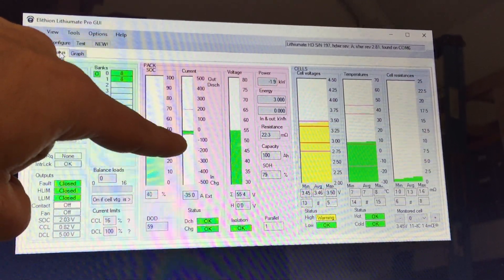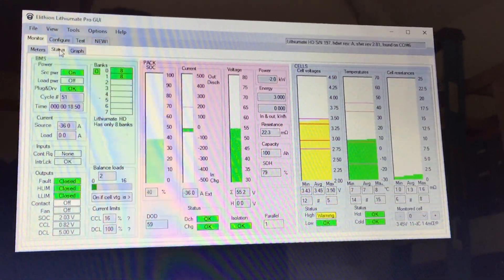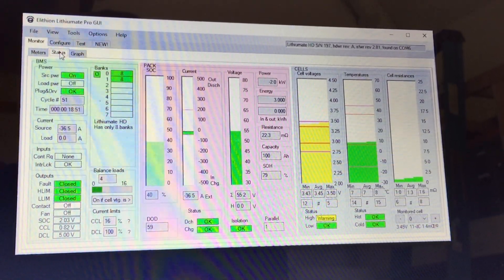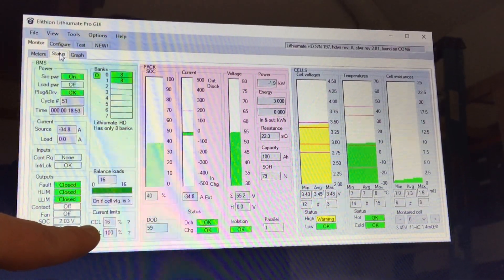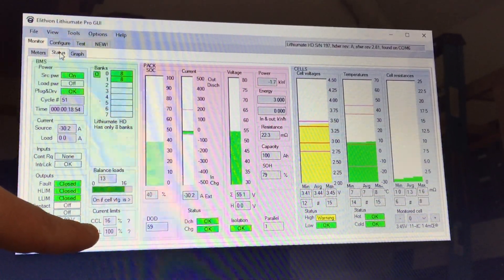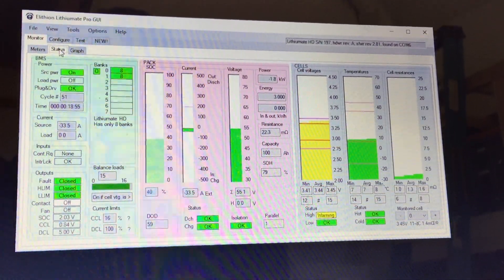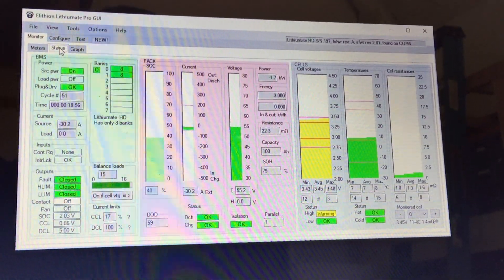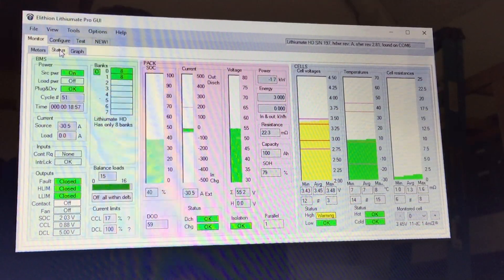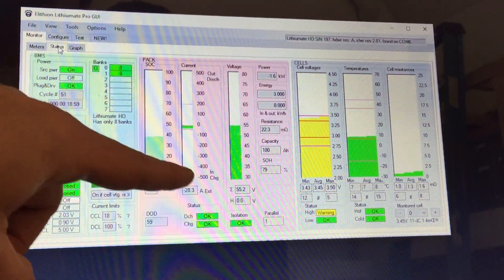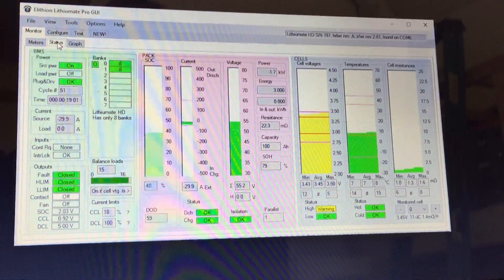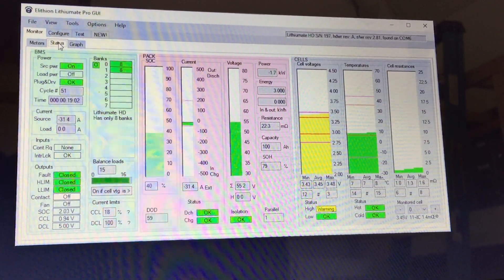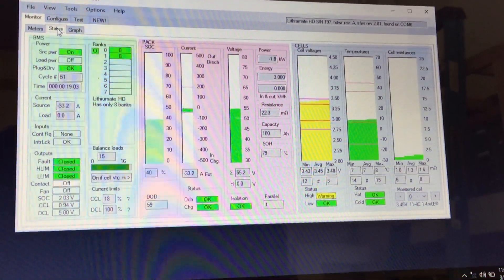The red line shows the maximum allowable charge rate, which is a function of the charge current limit, currently showing 16-17% of 200 amps max charge rate.